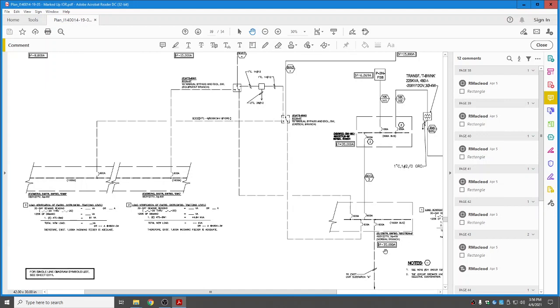when we lose utility power from the transformer, within 10 seconds the generator's got to kick in and provide full power, which makes these automatic transfer switches click over and run on e-power and provide your life safety equipment or critical branch power to the necessary equipment. Okay, that's enough for this page.